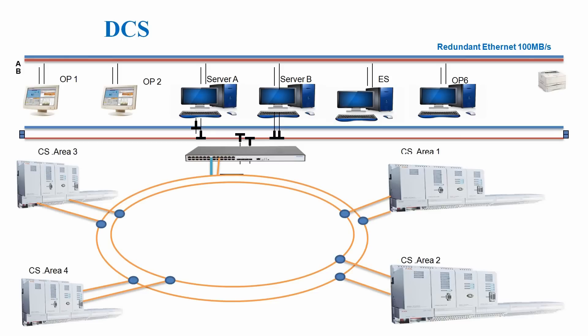DCS is connected to sensors and actuators, and it uses set points to control the flow of material throughout the process plant. The most common example is set point control. DCS itself sends a set point — for example, for pressure. The pressure measured by the transmitter is sent back to the controller, which reads it, and based on the program written, instructs a valve or an actuator to operate so that the process reaches and keeps the desired set point required by the process.